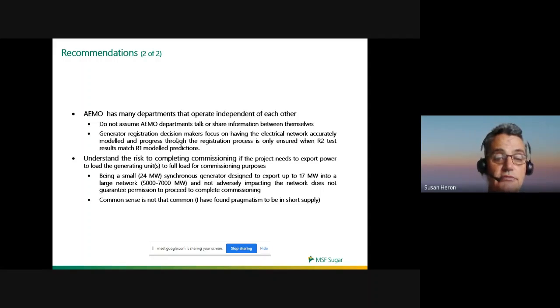It's really vital that your R2 test results match your R1 model predictions. Understand the risk of completing commissioning - I think I went in undercooked with that - if you need to export power to commission the plant, you then have to go through the R1, R2 process to ramp up to that.